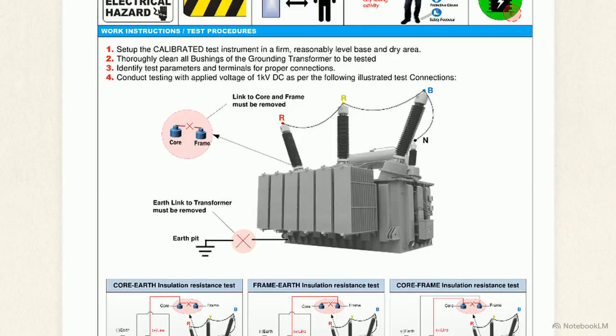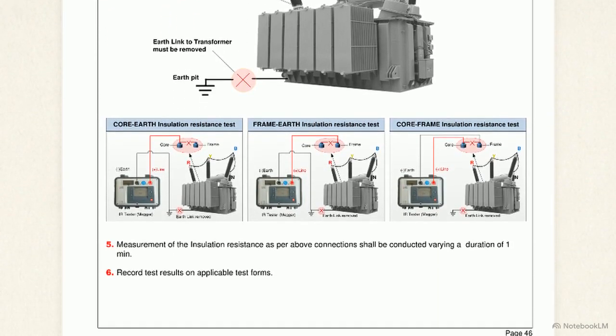The core and frame require their own insulation checks. Looking at these callout circles, technicians must explicitly remove the links tying the core, frame, and earth together before applying a 1 kV DC test. As shown in these 3 lower panels, we validate 3 distinct paths: core to earth, frame to earth, and core to frame, ensuring total internal isolation.